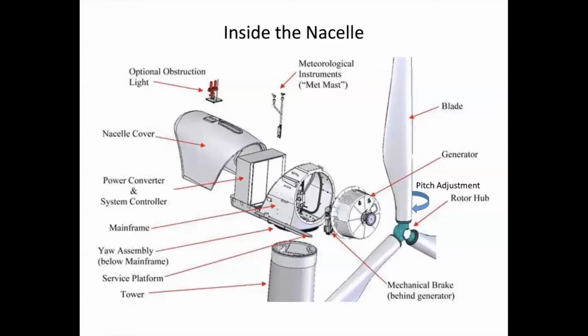It's direct current. That DC electricity then goes into this power converter system controller, and it gets converted to AC, 60 cycle AC at very high voltage. The standard voltage coming off an offshore wind turbine is 66 kilovolts—that's 66,000 volts, three-phase electricity at 60 cycles. So that's kind of what it looks like.